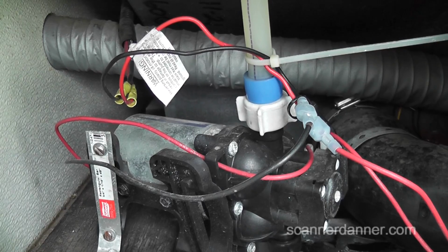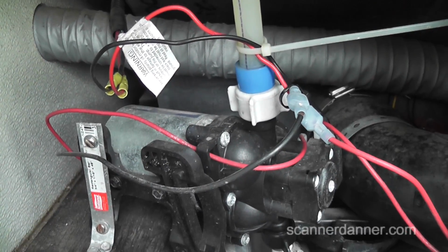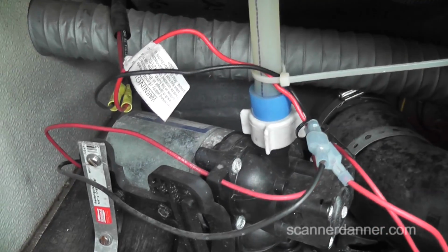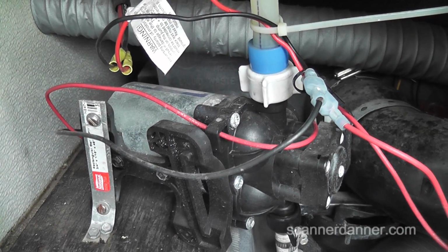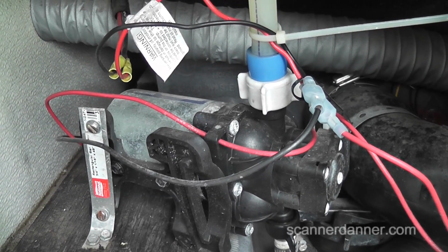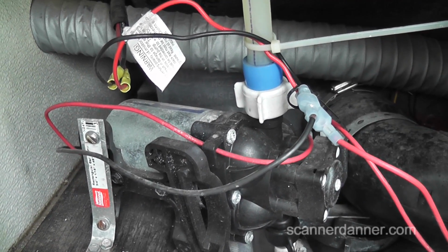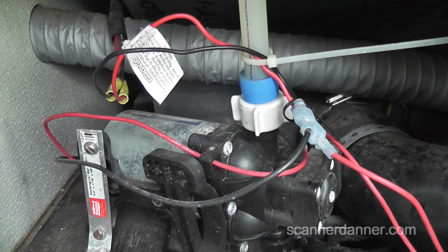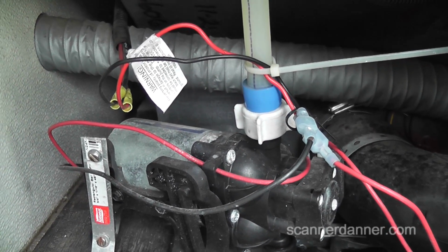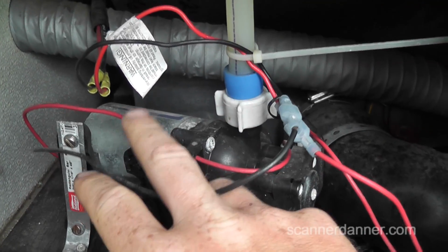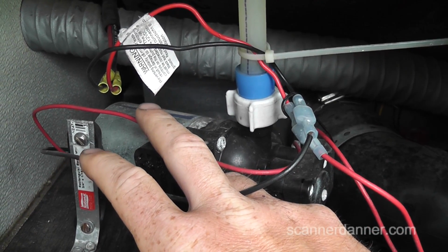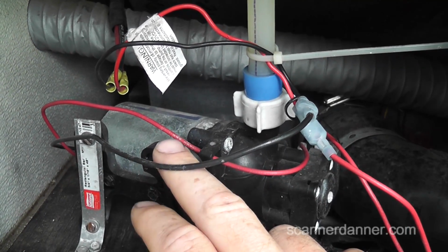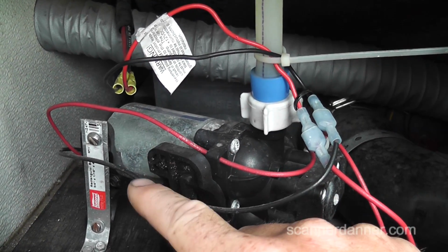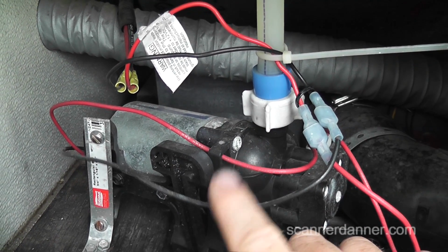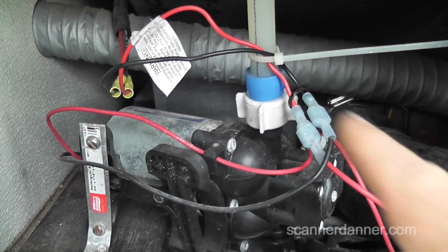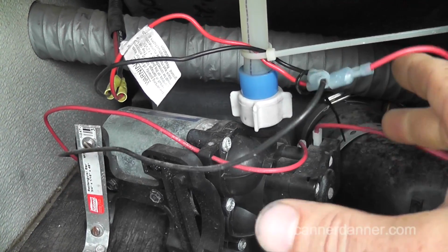I'll let you guys hear it again as I'm opening the valve. Alright, so what we're going to do first is, if the motor's actually failing, we should have a constant 12 volts and a constant ground on these two wires right here. If I find that either one of these is dropping out while the motor is clicking on and off, that suggests we have a connection issue or a switch issue up here, and so we'll kind of backtrack.